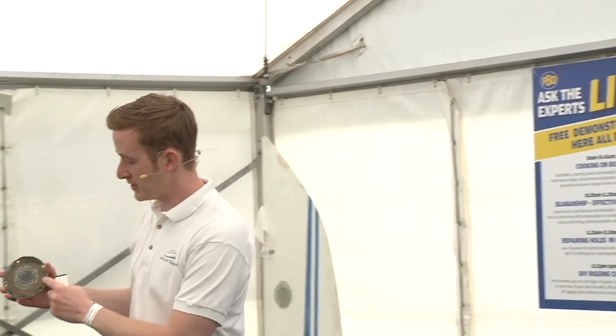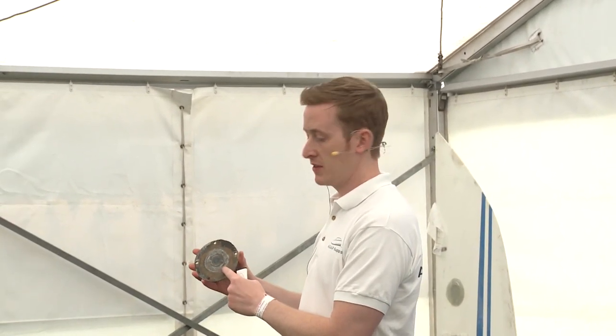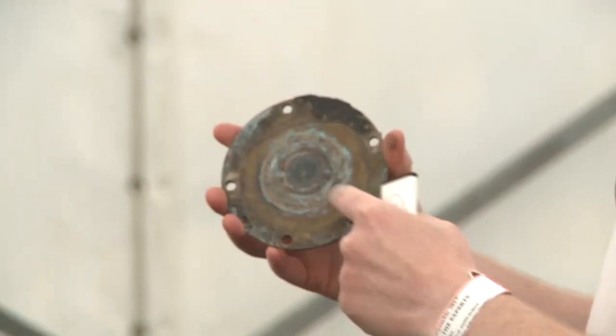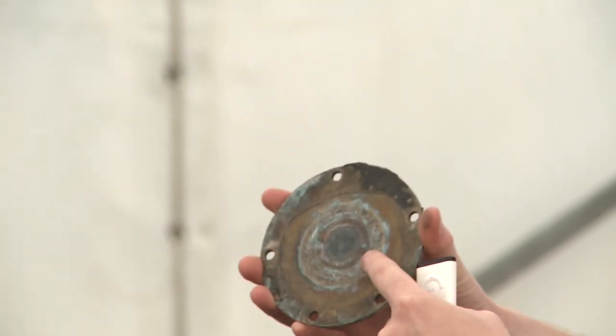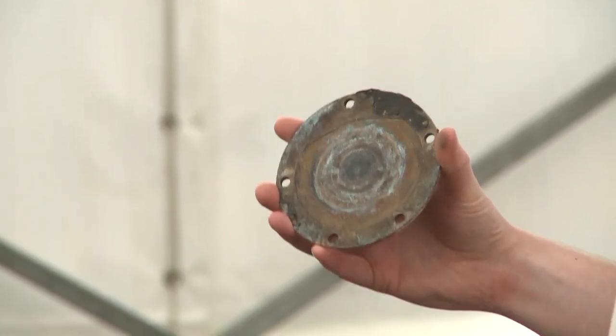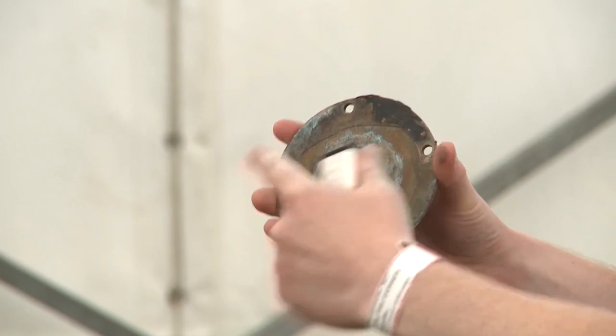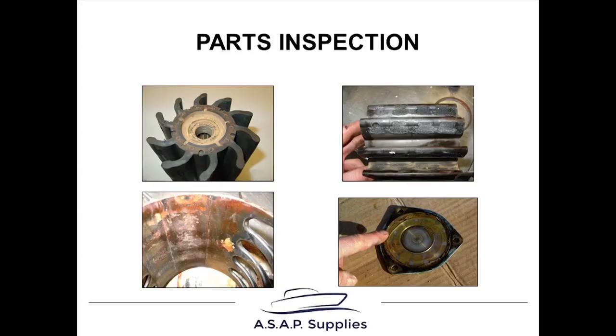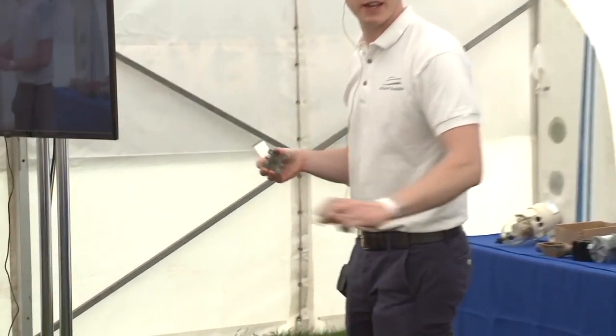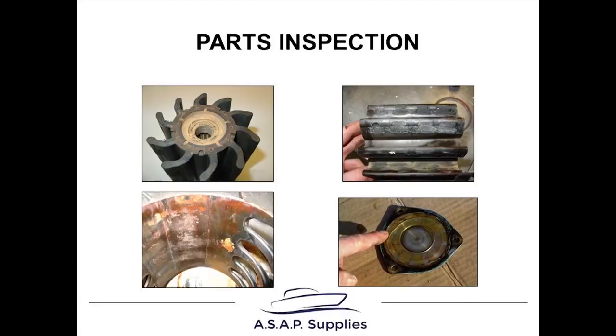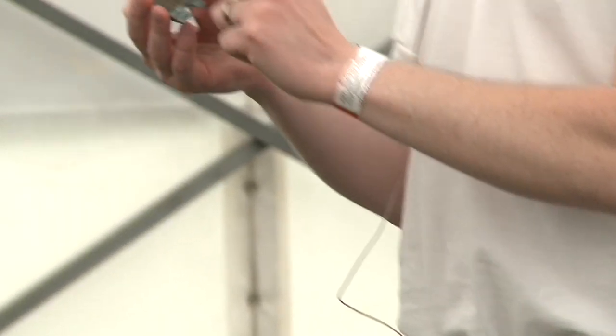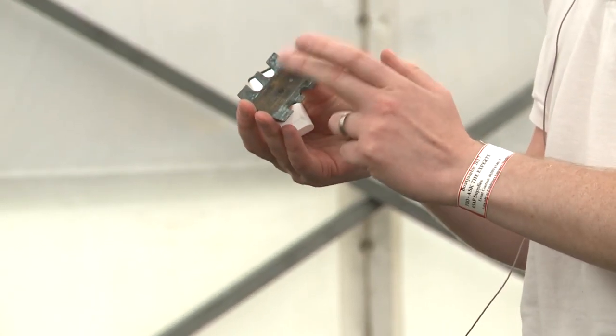You can start to see where the rubber impeller starts wearing away on the brass. If that happens too much on the cam, the wear plate, and the end cover, the pump can't self-prime as well, because it'll start moving water around in those pieces rather than sucking it up through the strainer. Also, the cam's points will get very sharp and start cutting into the impeller - you can see in the top right picture where it started cutting in, which kills your impellers quicker. It should be nice and smooth, but that thickness gets decreased, so it's not pumping the amount of water it should.